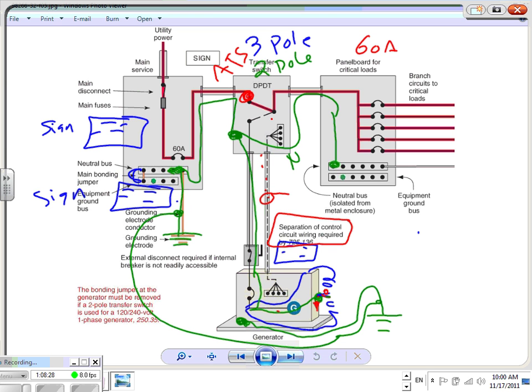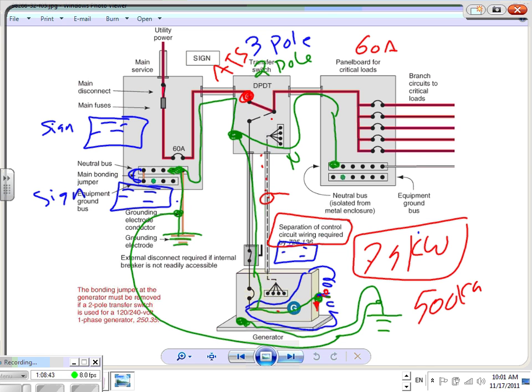So you can get up to 7.5 kW this way or even higher. I hate to put any value on that one. Generators for homes, I mean, you can get as high as you want to go, but you can put 500 kVA, 500 kW here this way. You can go as high as you want. For the most part, you don't go higher than 500 kW for a lot of applications. If you go 2 meg and 3 meg, you start doing it slightly differently. We call it paralleling. Any question, guys, about this?